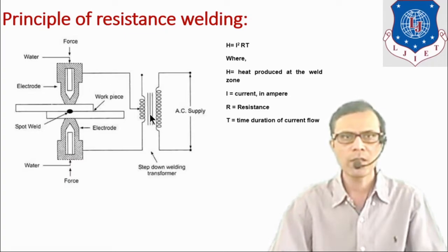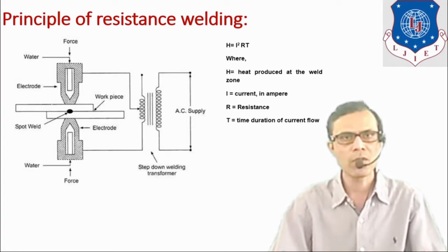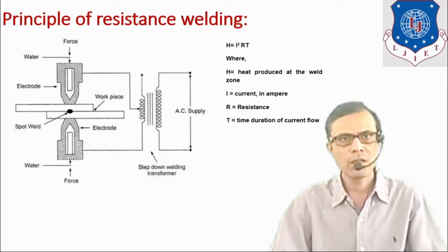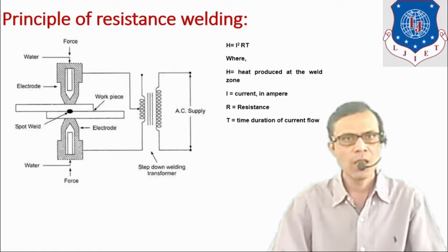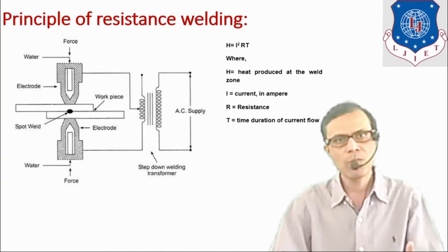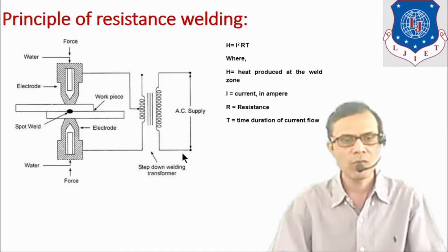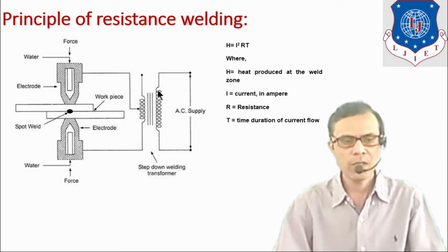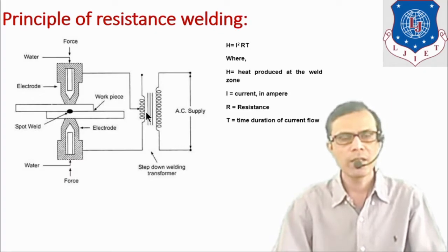A step-down transformer is used, which decreases the supply voltage — generally it ranges from 4 to 12 volts — and by that way increases the current flowing through the circuit. Generally its value can be up to 10,000 amperes for welding purpose, though maximum values can go up to 50,000 amperes. So by using this transformer we are decreasing supply voltage and increasing current flow.